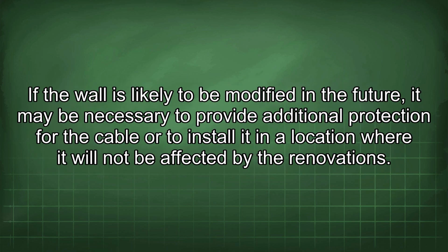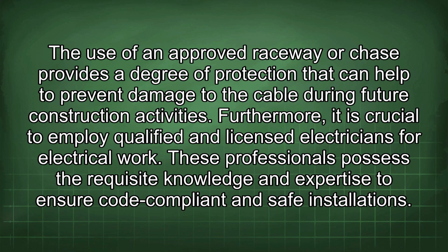If the wall is likely to be modified in the future, it may be necessary to provide additional protection for the cable or to install it in a location where it will not be affected by the renovations. The use of an approved raceway or chase provides a degree of protection that can help to prevent damage to the cable during future construction activities.